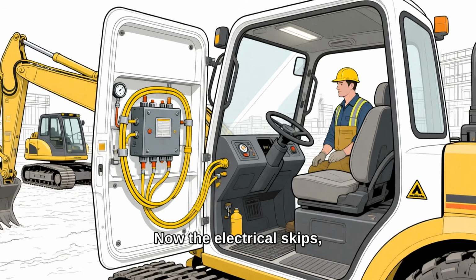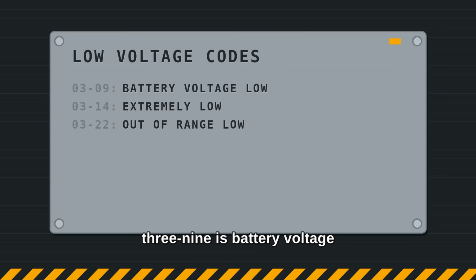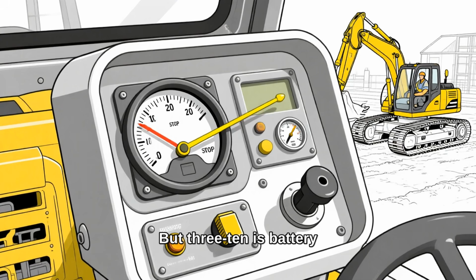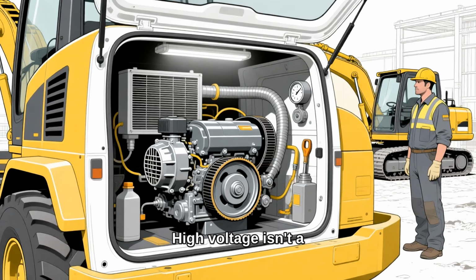Now the electrical skips, the cheapest ones to fix and the easiest ones to postpone. 309 is battery voltage low, 314 is extremely low, 322 is out of range low, but 310 is battery voltage high and 311 is extremely high. Those point the other direction. High voltage isn't a tired battery. That's the charging side, and it doesn't heal on its own.